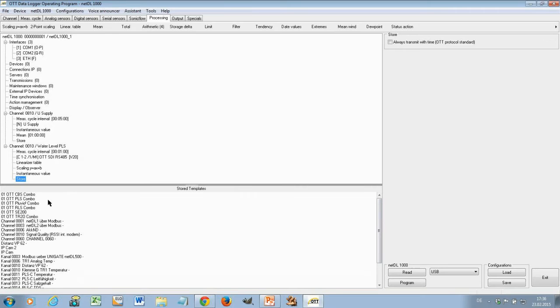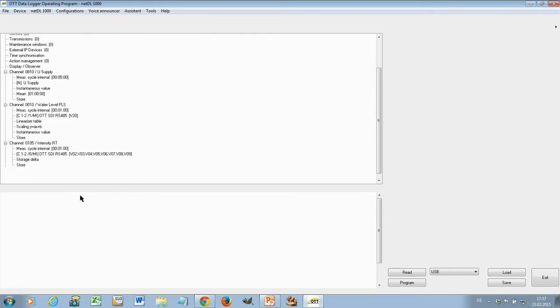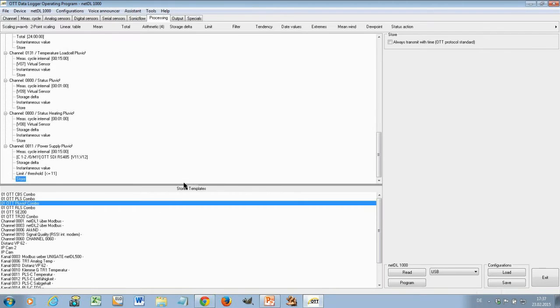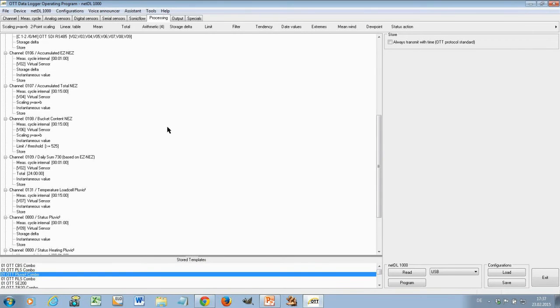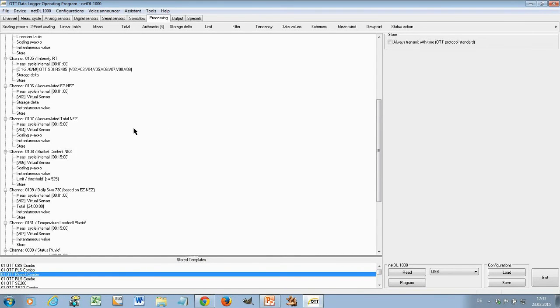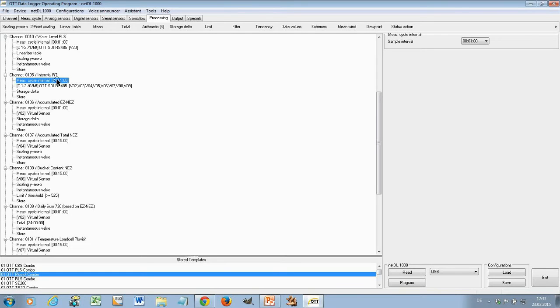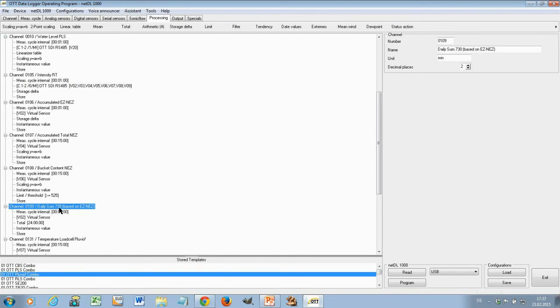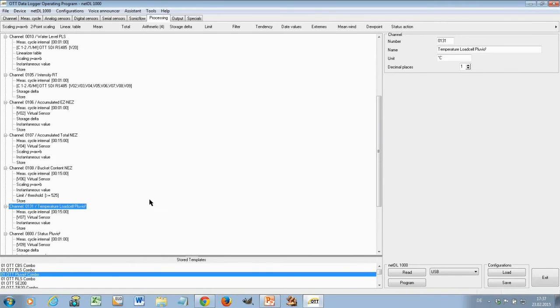You see here also some other templates like Pluvio Combo. Those are pre-defined templates and I will show you how this looks like. You take this, put it up here and now I have here a complete Pluvio configuration. It starts here with channel 105, 106, 107, 108. This is all from the template and now you can adjust it. You can adjust here maybe the measurement interval if you want to change it. You can say, okay, I don't need all this stuff. I don't need the daily sum, so I just delete it. So, you can use this template and modify it to your needs. That saves you also a lot of time and efforts doing such configurations.